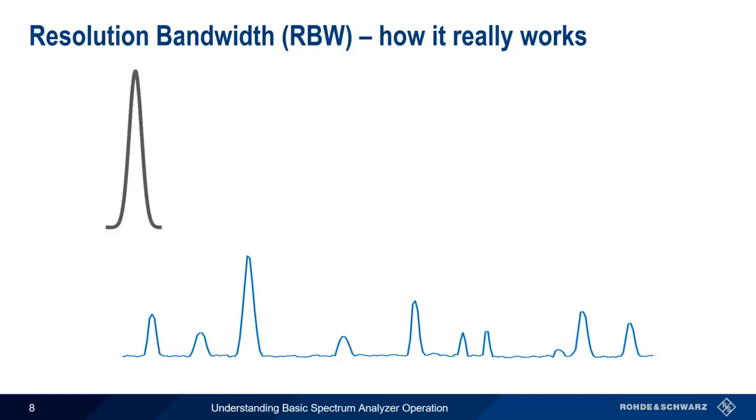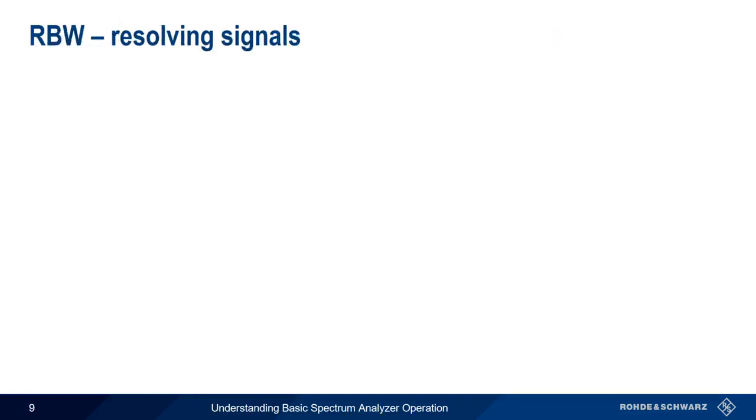Next, let's examine two ways that resolution bandwidth plays a critical role in spectrum analysis, namely separating signals and noise. Let's start with signal separation. As the name implies, one of the things that resolution bandwidth affects is our ability to separate or resolve closely spaced signals. For example, if we have two narrow signals, we can only separate them if our resolution bandwidth is smaller than the distance between these two signals.